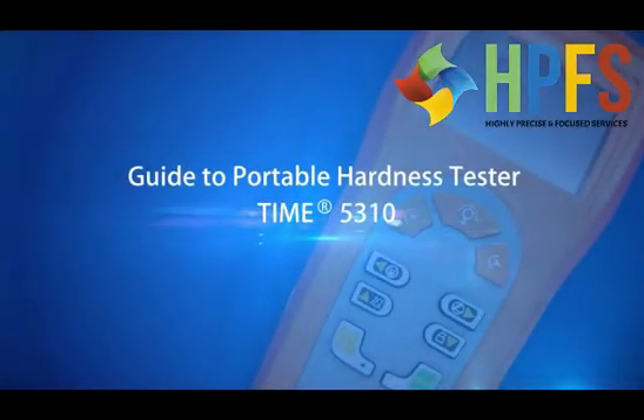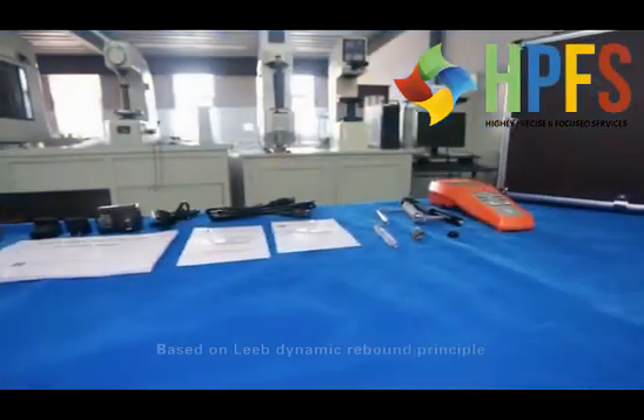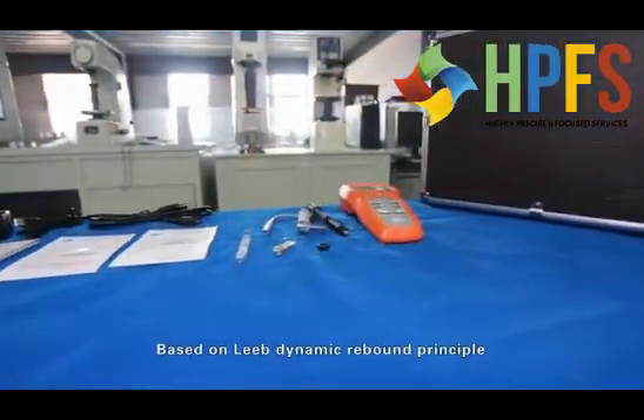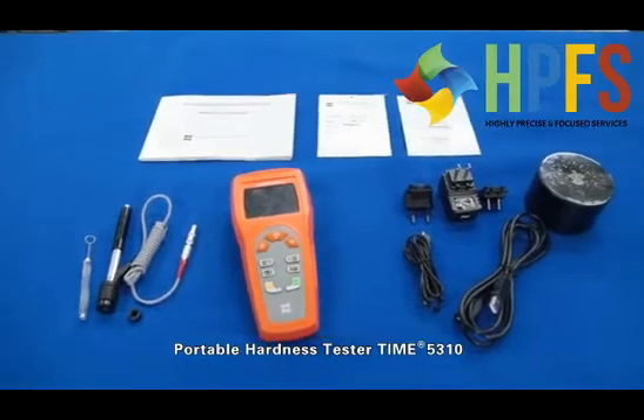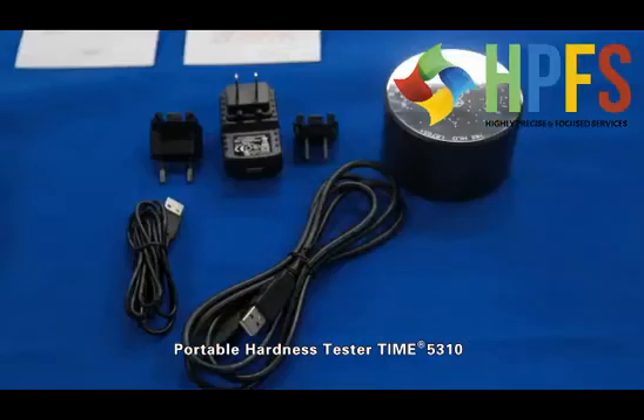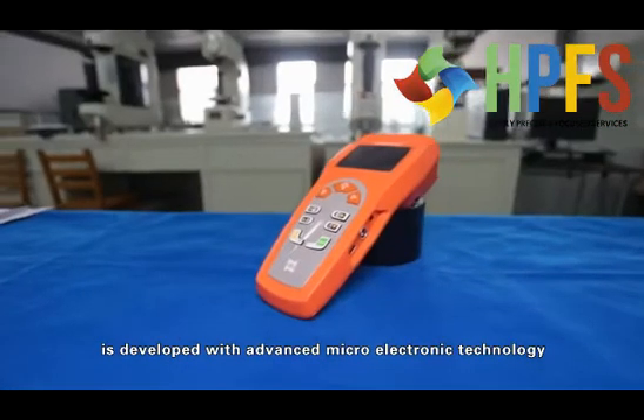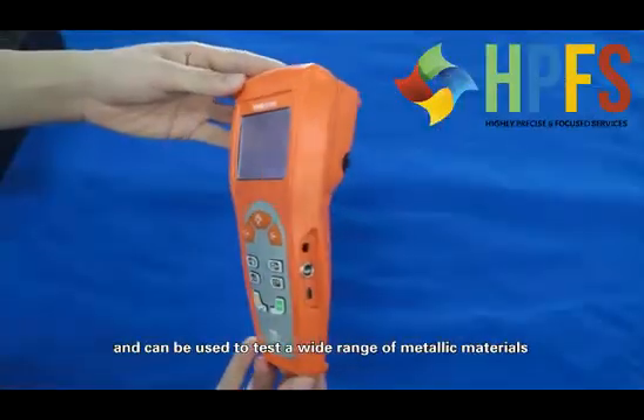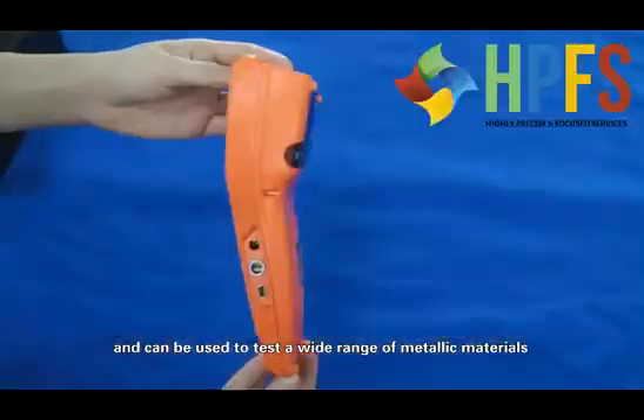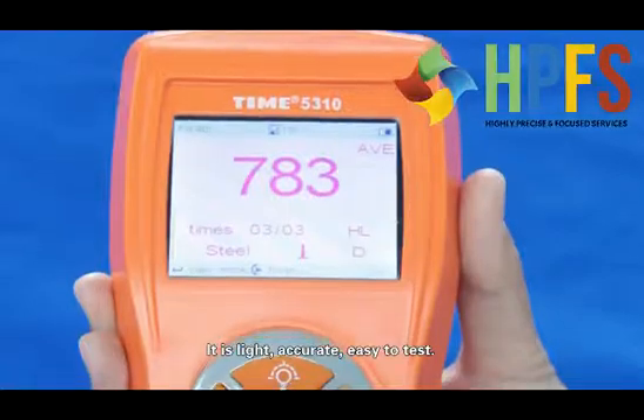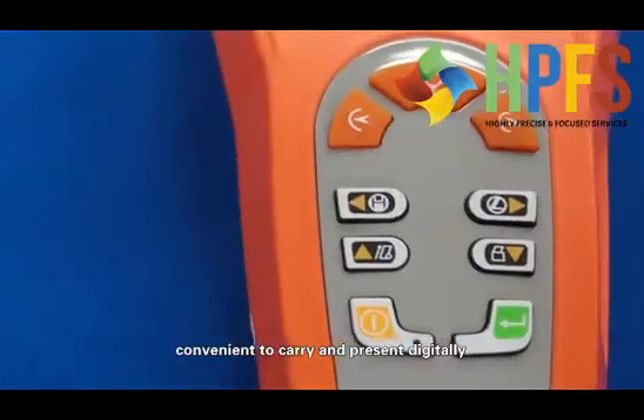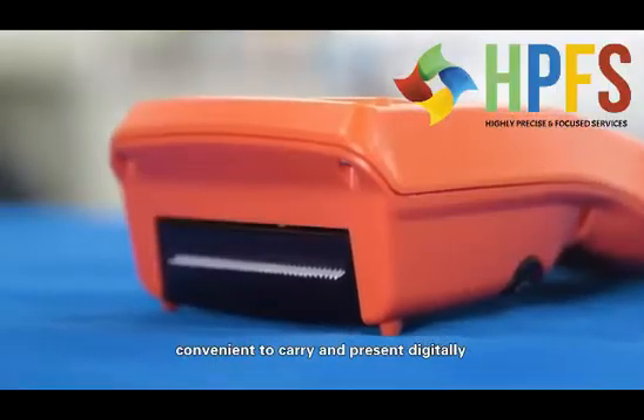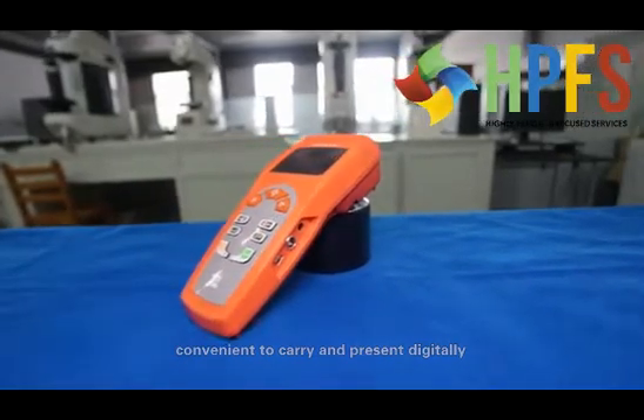Guide to portable hardness tester, Time 5310. Based on the Leeb dynamic rebound principle, portable hardness tester Time 5310 is developed with advanced microelectronic technology and can be used to test a wide range of metallic materials. It is light, accurate, easy to test, convenient to carry, and presents results digitally.